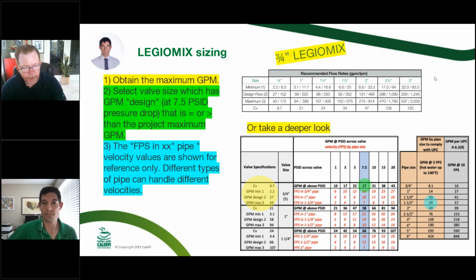The big takeaway is, it's come up 3 times now, I think, that just because you've got 1.25 inch or 1.5 inch piping going into the building does not mean that the Legio mix or whatever mixing device you're using is going to be the same size. If you do take it down, whether it's 3/4 or 1 inch, I think you could argue for either in this scenario. Just understand that does not mean that you've got 30 feet of 1 inch or 3/4 inch pipe coming off of it. You're going to have all kinds of problems with that, and I would be terrified of seeing what the pressure drop and velocity would be going through the piping on that.